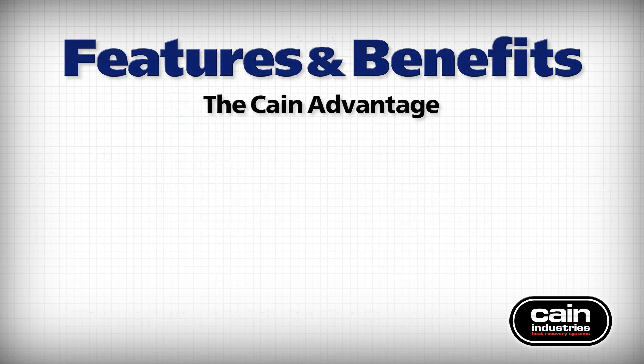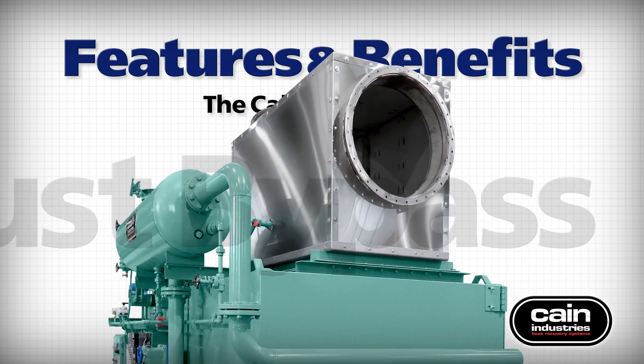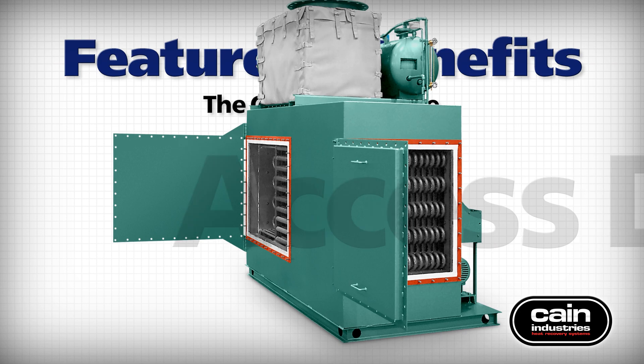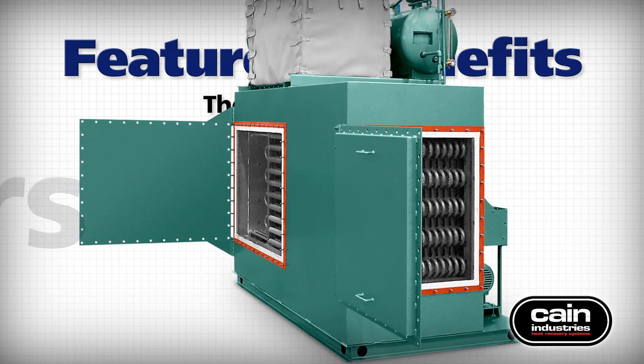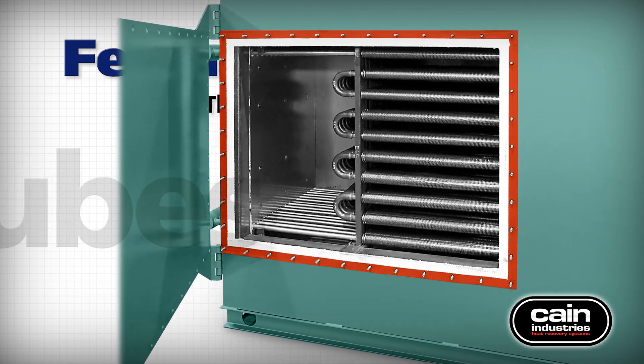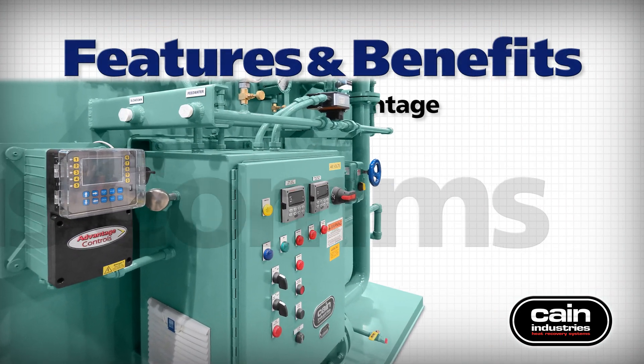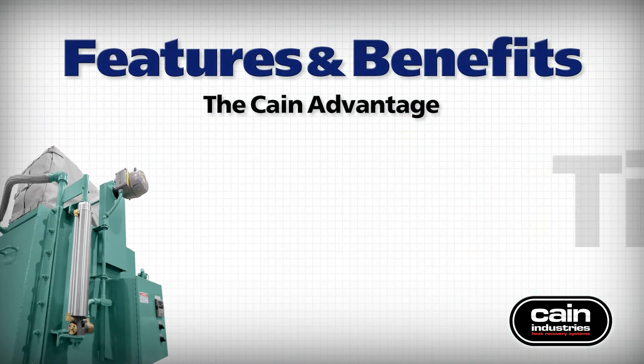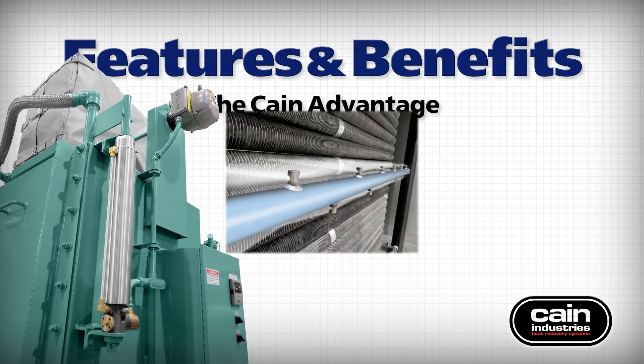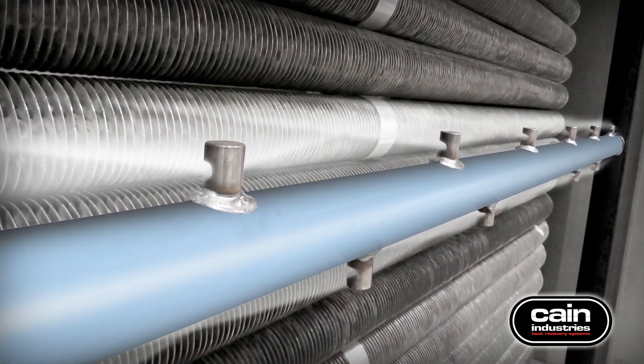Cain Industries' standard equipment features unmatched benefits. The ESG-1 and HR-SR product lines are typically provided with a stainless steel exhaust bypass for full exhaust flow control. Full panel hinged access doors allow easy access for fin tube inspection and cleaning. Individual removable fin tubes or modular fin tube racks allow for heat transfer surface repair in the field. Modbus communications provide remote equipment monitoring and operation control. An optional automatic timed soot blower provides optimum performance when burning fuels that cause soot buildup. A knife-edge concentrated air or steam spray flow pattern is used to blast soot from fin tubes into the exhaust stream and out of the unit.